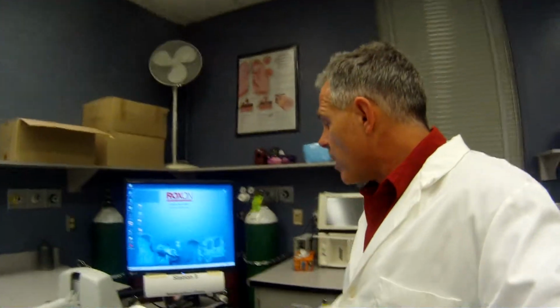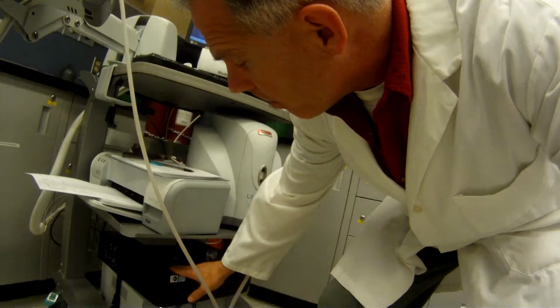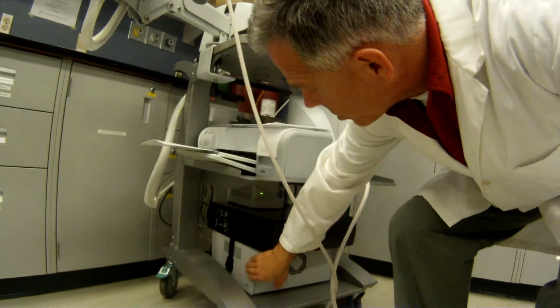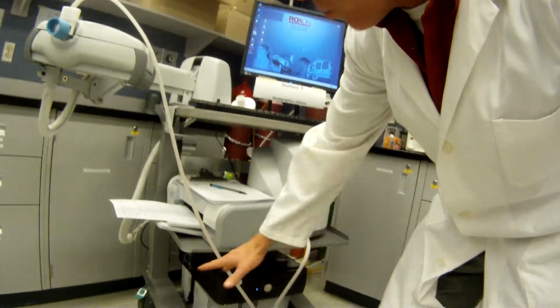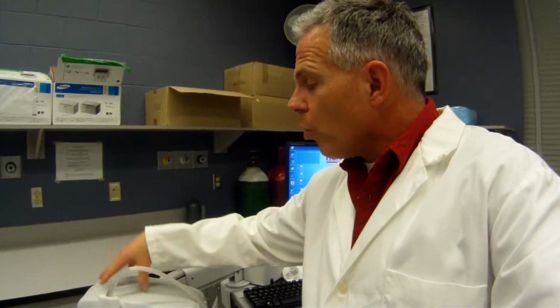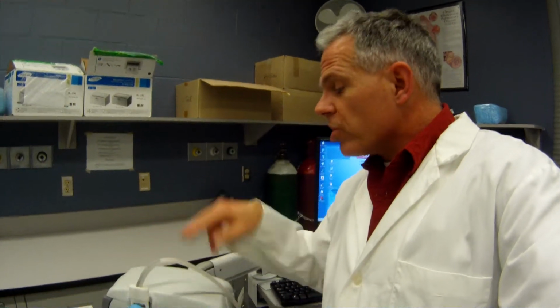You also want to make sure that you have the proper test gases and how that'll be hooked up, just in case you ever came into the pulmonary function lab and those were not hooked up. So you can see how to set those up. Now on the backs there's specific pressures that those gases have to be regulated to. So that's kind of the background stuff. Other than that, it's just a basic computer, and we have here our gas controlling unit. All right, so that's where the computer's hooked up and controls all the gases and controls this device right here, which is both our pneumotach and our gas controller.